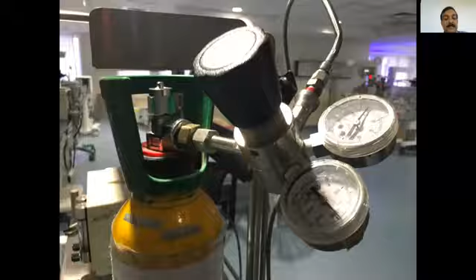And this is the regulator system. This is where we connect the nitric oxide to our SLE 5000, 6000 or 3000 units, or any conventional ventilation. It has to be connected. This is called the nitric oxide delivery kit, and it costs about 6,000, which is a disposable circuit. This disposable circuit is connected to the nitric oxide monitoring system.